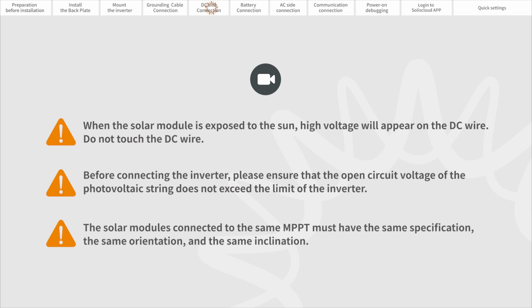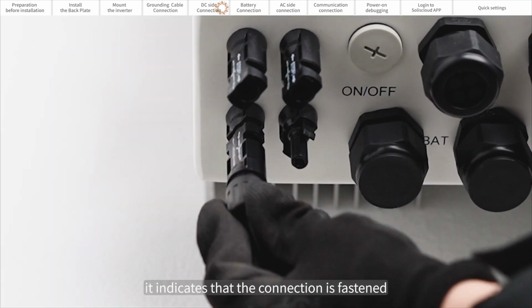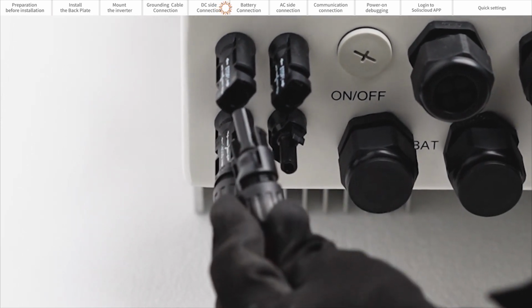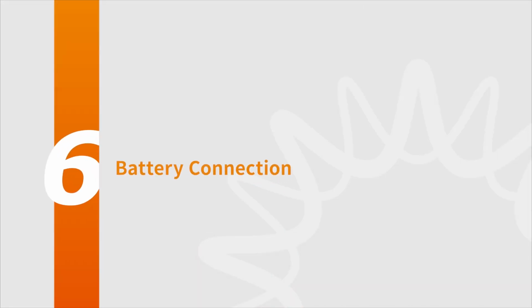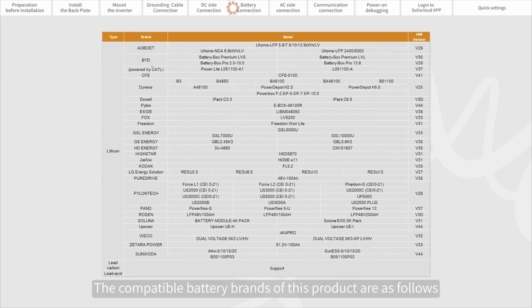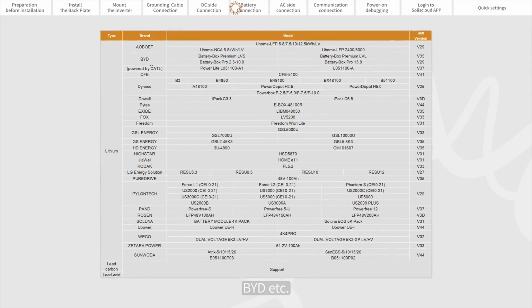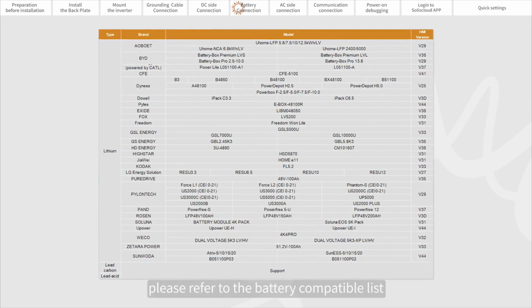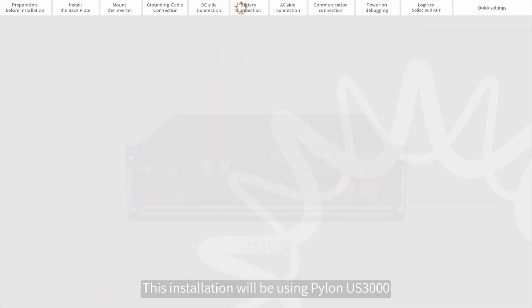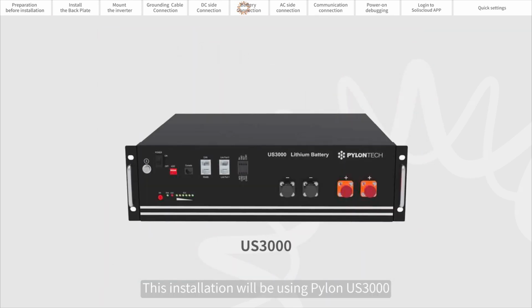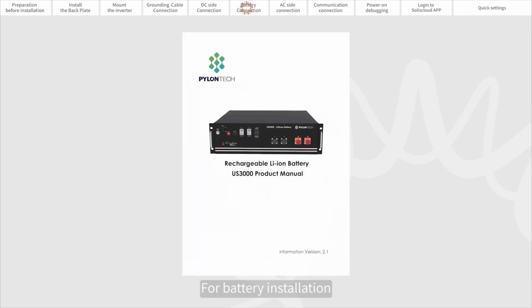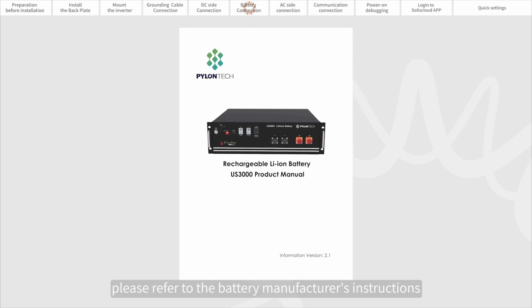The solar modules connected to the same MPPT must have the same specification, the same orientation, and the same inclination. When you hear a click sound, it indicates that the connection is fastened. Part 6. Battery connection. The compatible battery brands of this product are as follows: Pylon, BYD, etc. Please refer to the battery compatibility list on the Solis website for details. This installation will be using Pylon US3000C. For battery installation, please refer to the battery manufacturer's instructions.